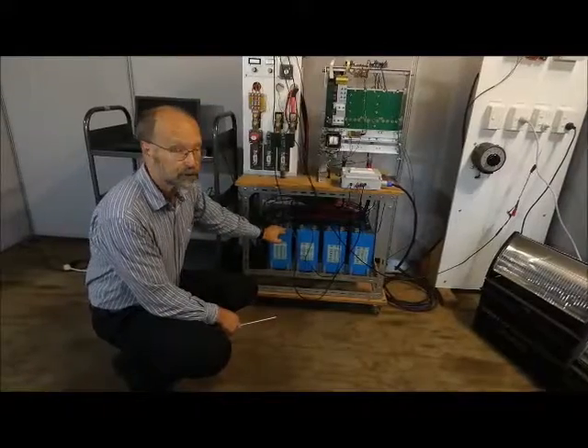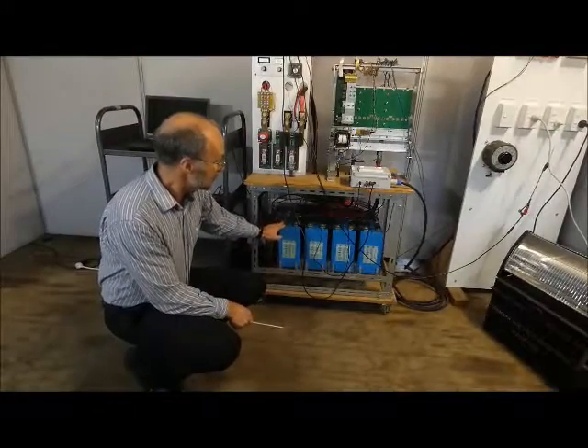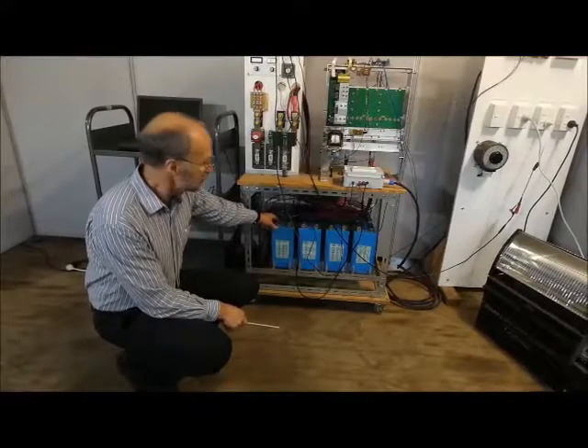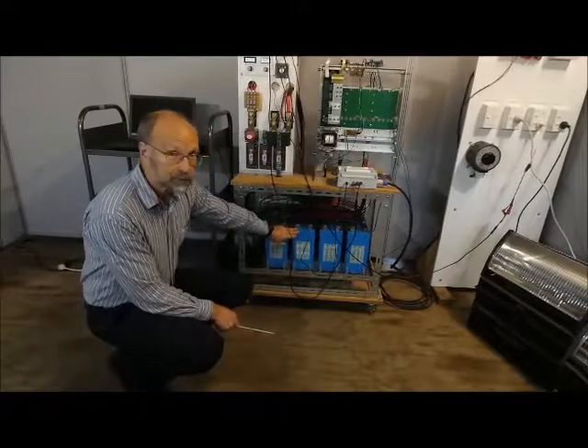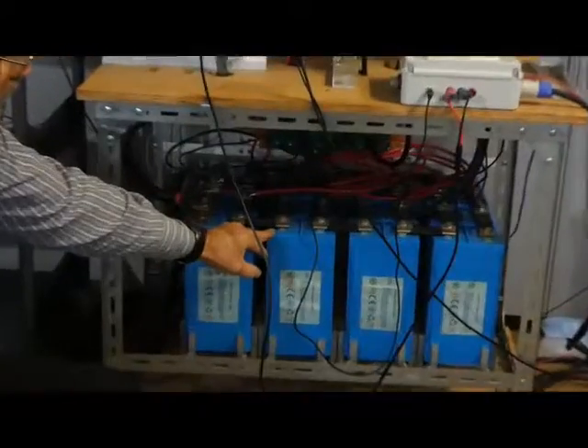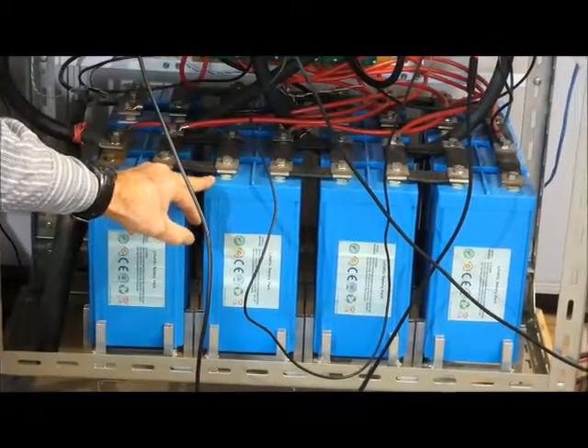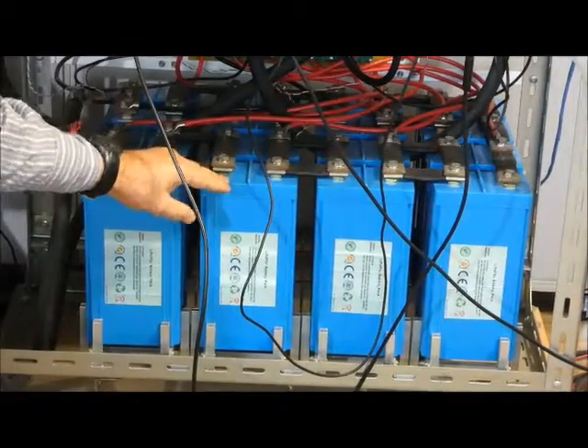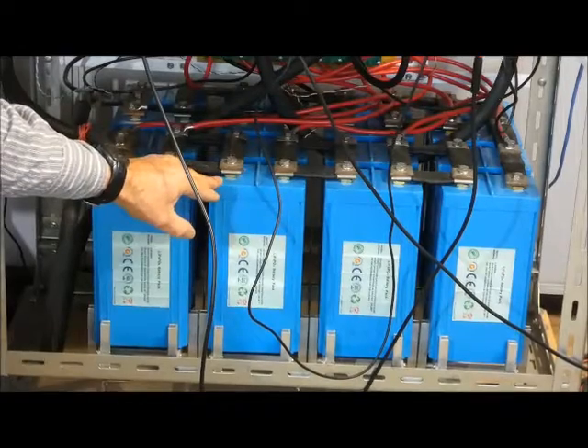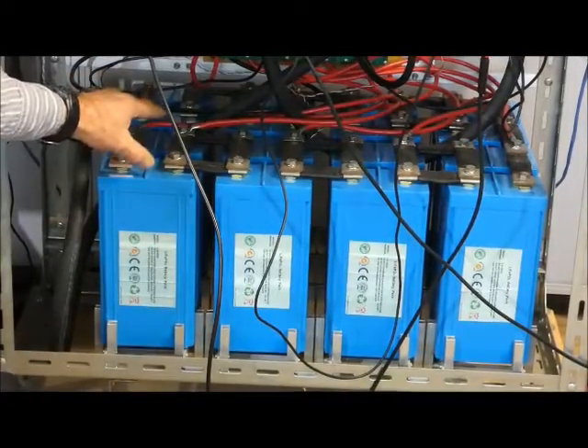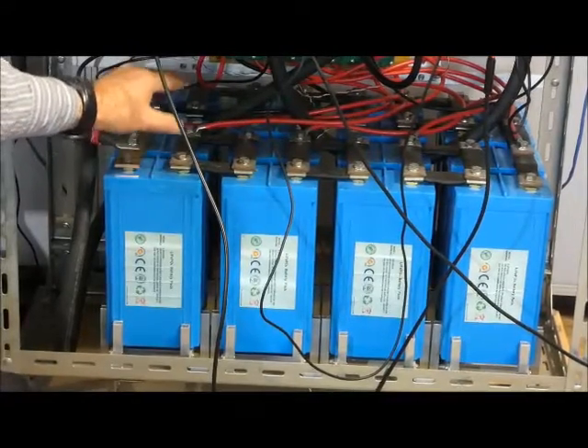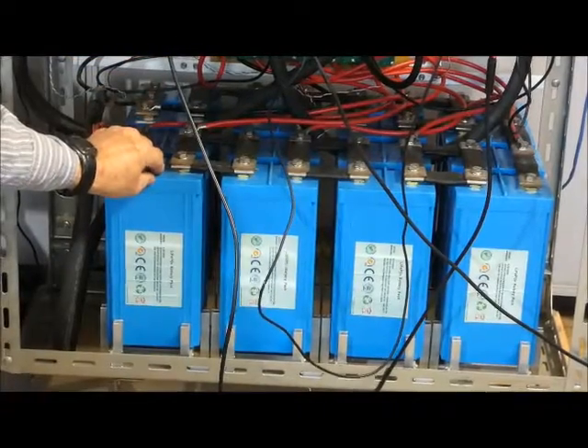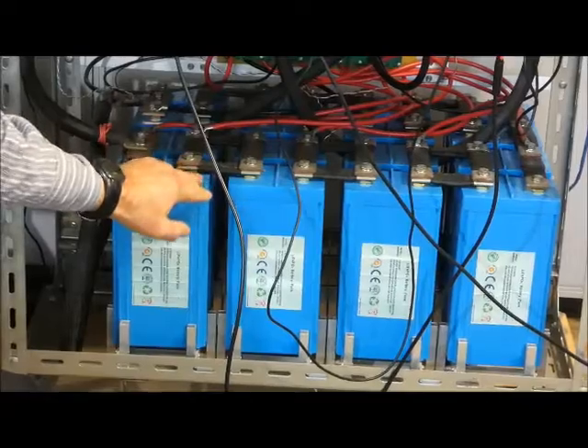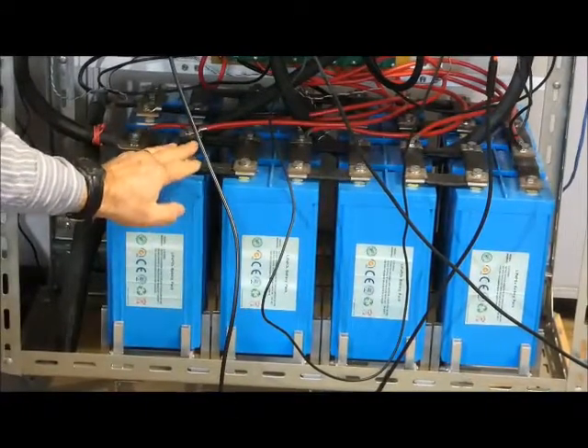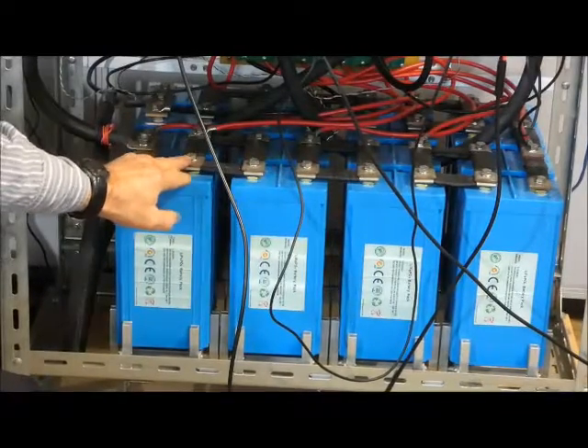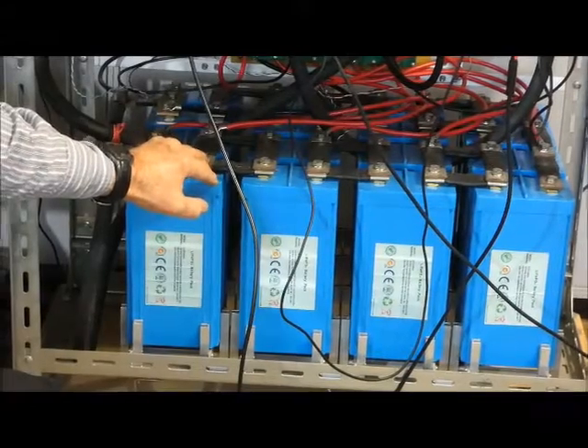This is the battery for the demonstration system. Not exactly the same as we'd put into a real installation, but using much the same technology. Inside each of these blue modules there are 32 cylindrical cells. They're 26650 cells, and that gives us 3.3 volts at 100 amp hours. These are lithium iron phosphate cells, and we have two modules connected in parallel to give us 200 amp hours, and then 8 of those sets in series to give a 26 volt battery. This gives us a usable capacity of around 5 kilowatt hours, which is suitable for demonstration purposes, and in fact would be quite suitable for running a small home system as well.